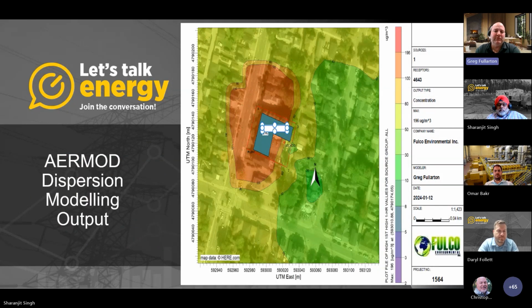This is just a sample output of what you would get. Let's assume the generator is on the roof here. When you run it through AERMOD dispersion modeling, you get an output similar to this, where the red represents the highest concentrations, up at about 196 micrograms per cubic meter. As you get further away and dilution takes over, you get into the green and darker green shades, which represent much lower concentrations. So it shows you the most serious impact is directly surrounding this building.